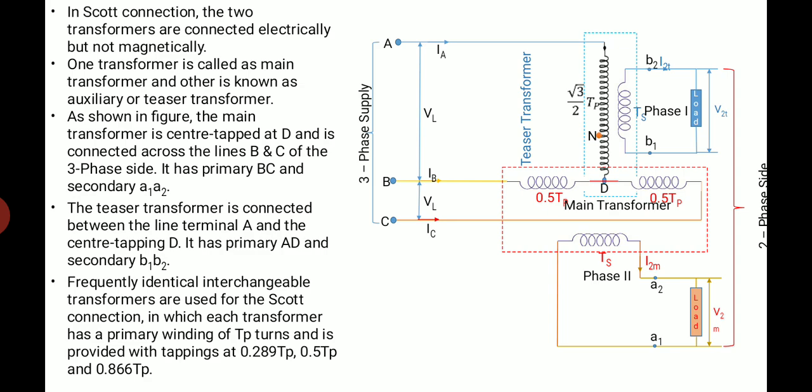As shown in this figure, the main transformer is center tapped at point D and is connected across the line terminals B and C of three-phase side. It has a primary BC and secondary A1, A2. The teaser transformer is connected between the terminals A and D and has the primary AD and secondary B1, B2. Frequently identical interchangeable transformers are used for the Scott connection in which each transformer has a primary winding of TP turns and is provided with tappings at 28.9%, 50% and 86.6% of primary winding turns.